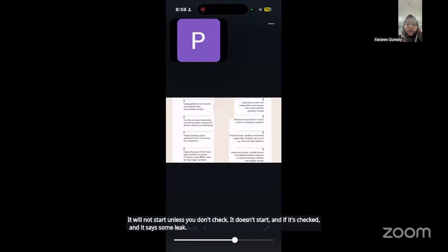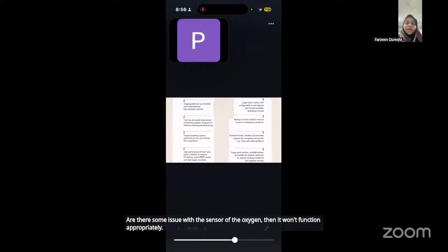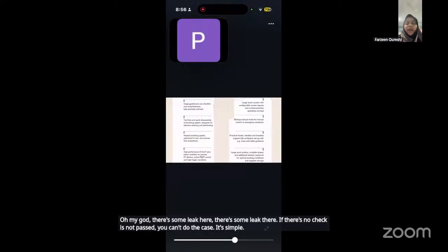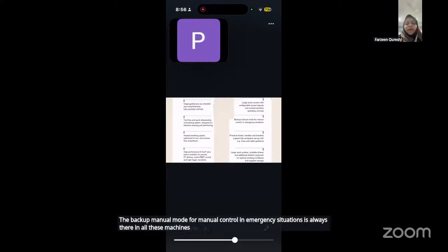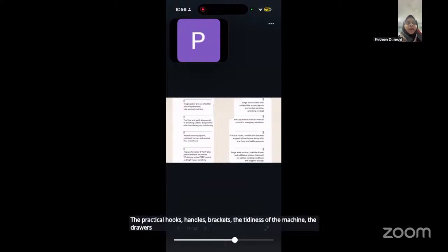And if it's checked and there's some leak or there's some issue with the sensor of the oxygen, then it won't function appropriately. So that's how the case gets stopped there and then. It's like nipping mischief in the bud. You don't have to struggle intraoperatively with, oh my God, there's a leak here, there's a leak there. If the check is not passed, you can't do the case. It's simple. The backup manual mode for manual control in emergency situations is always there in all these machines. The practical hooks, handles, brackets, the tidiness of the machine, the drawers, everything, the wheels, the wheels are so smooth that at a finger touch, they actually move like a meter front and back.